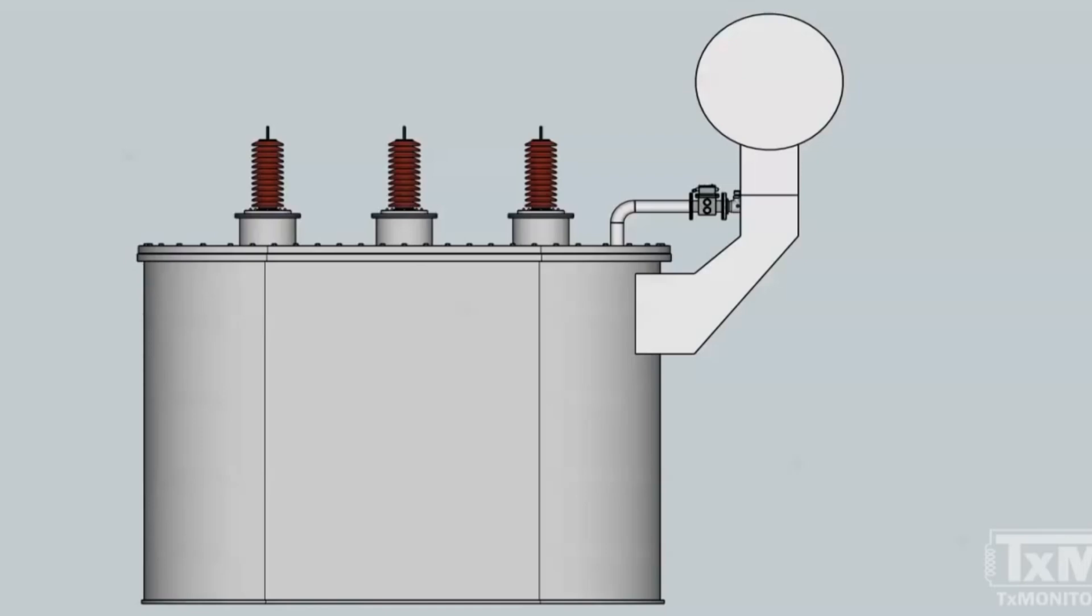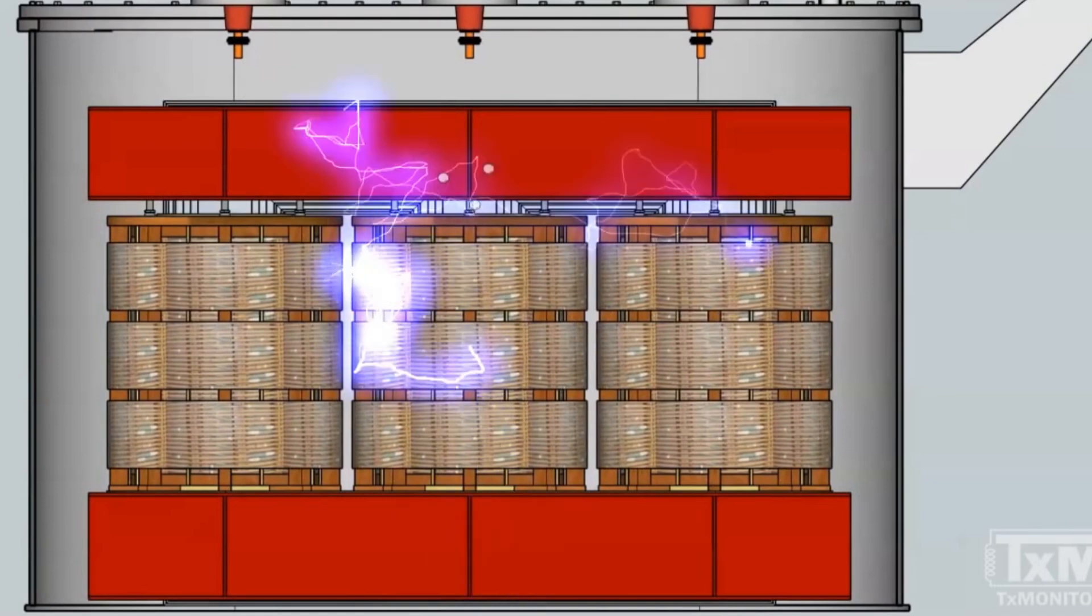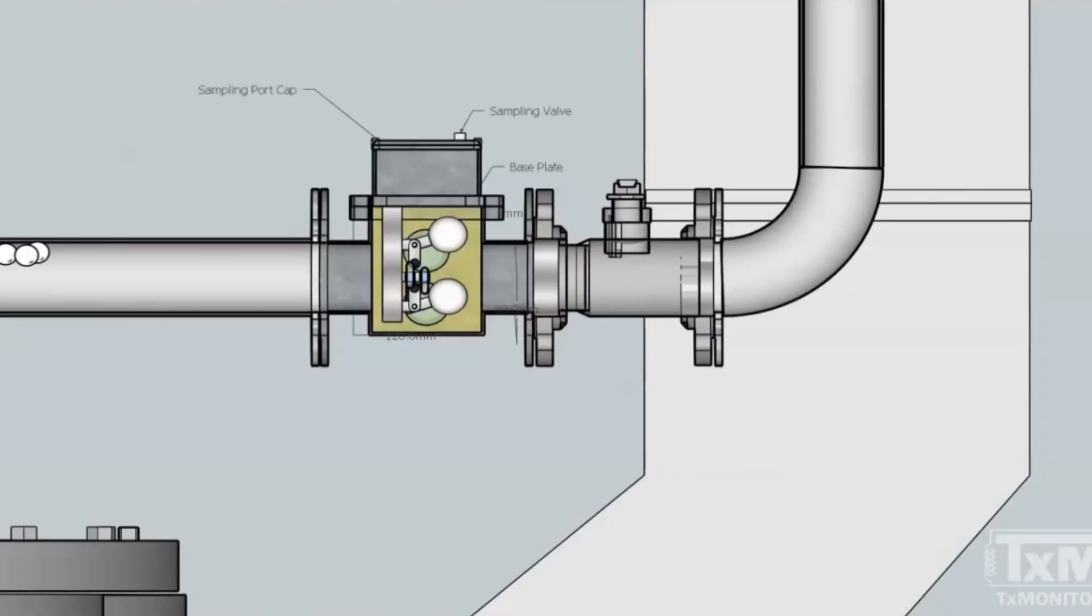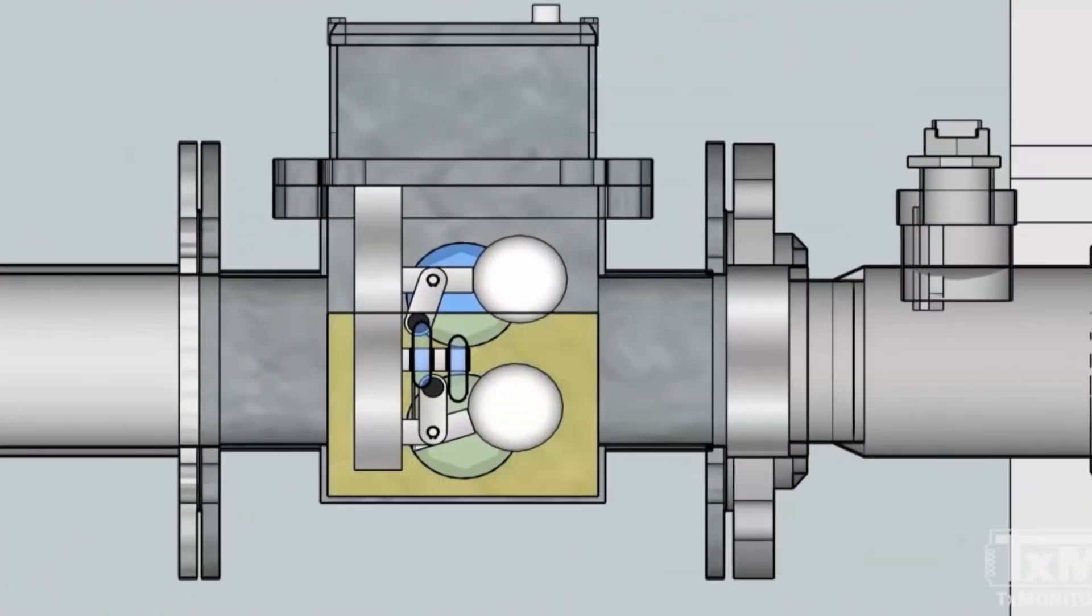When, for some reason, gases are not dissolved in the insulating liquid, they evolve in the form of bubbles. These bubbles tend to rise inside the unit and find their way to the conservator through the pipe, connecting the main transformer and the conservator tanks.